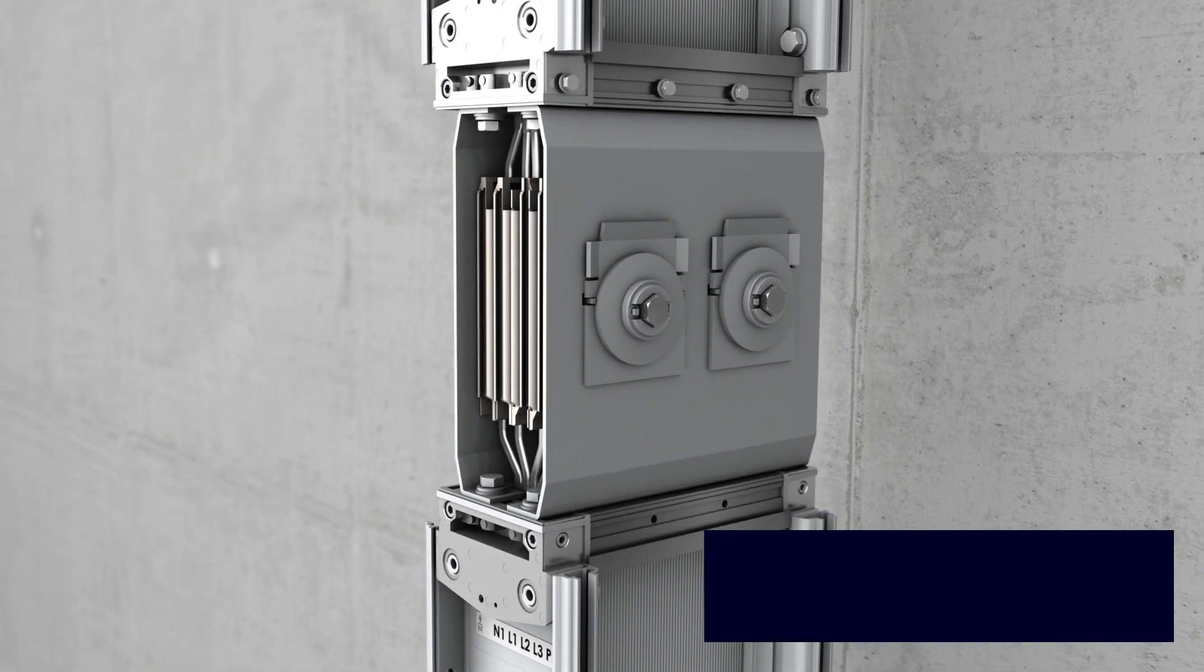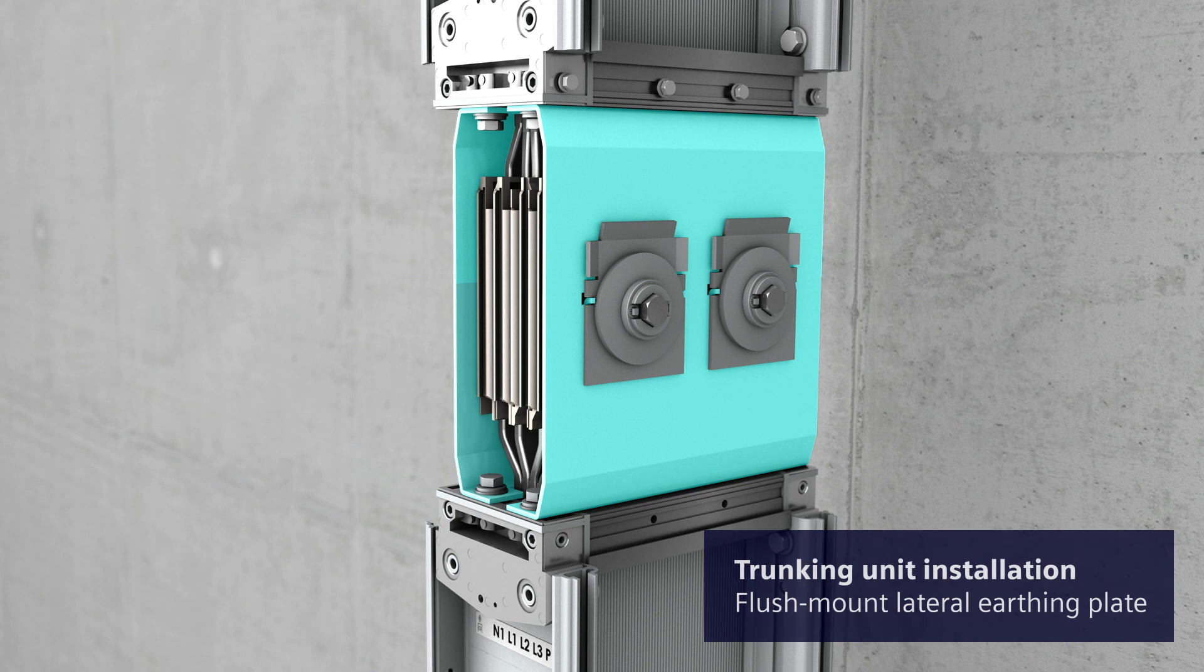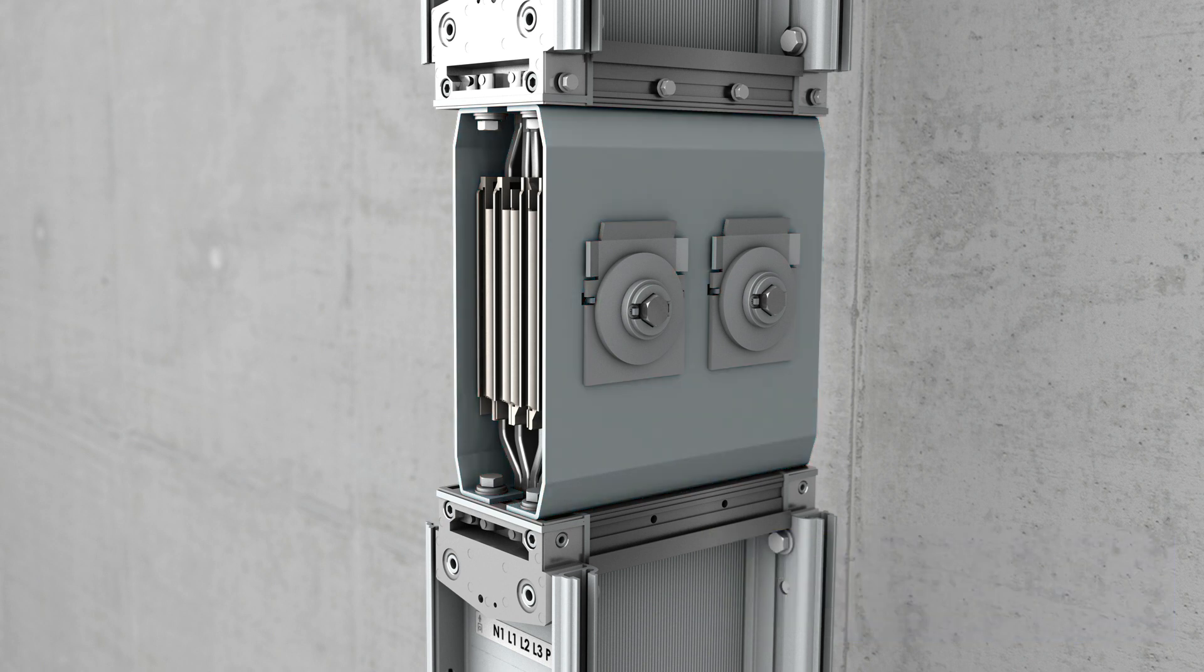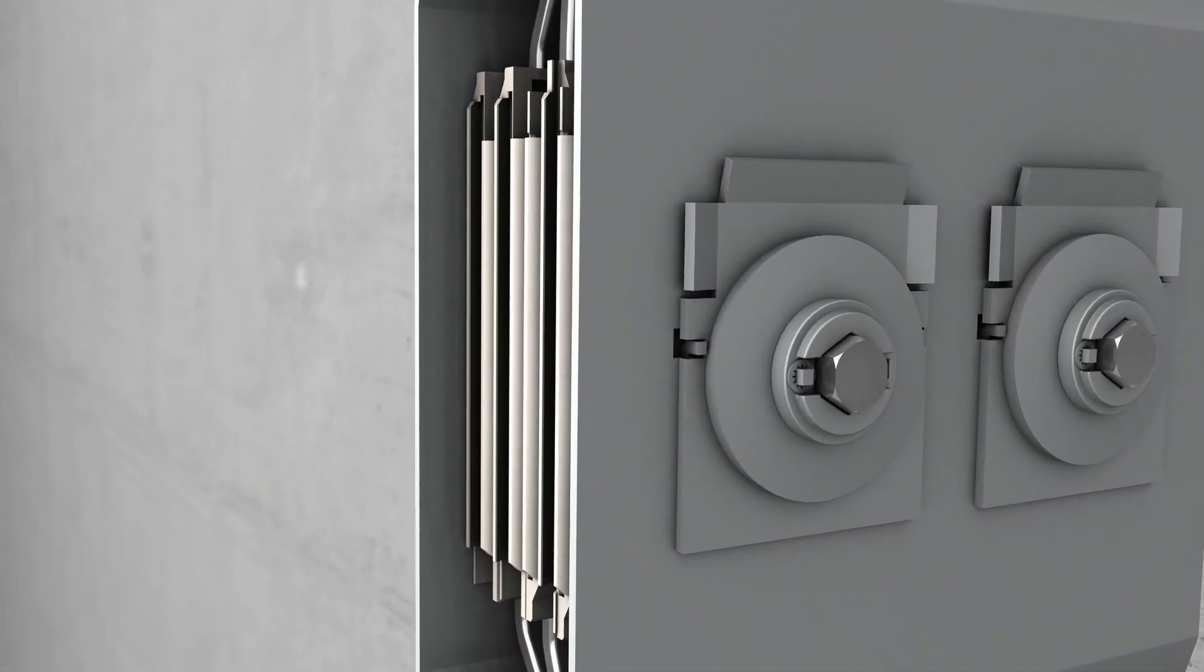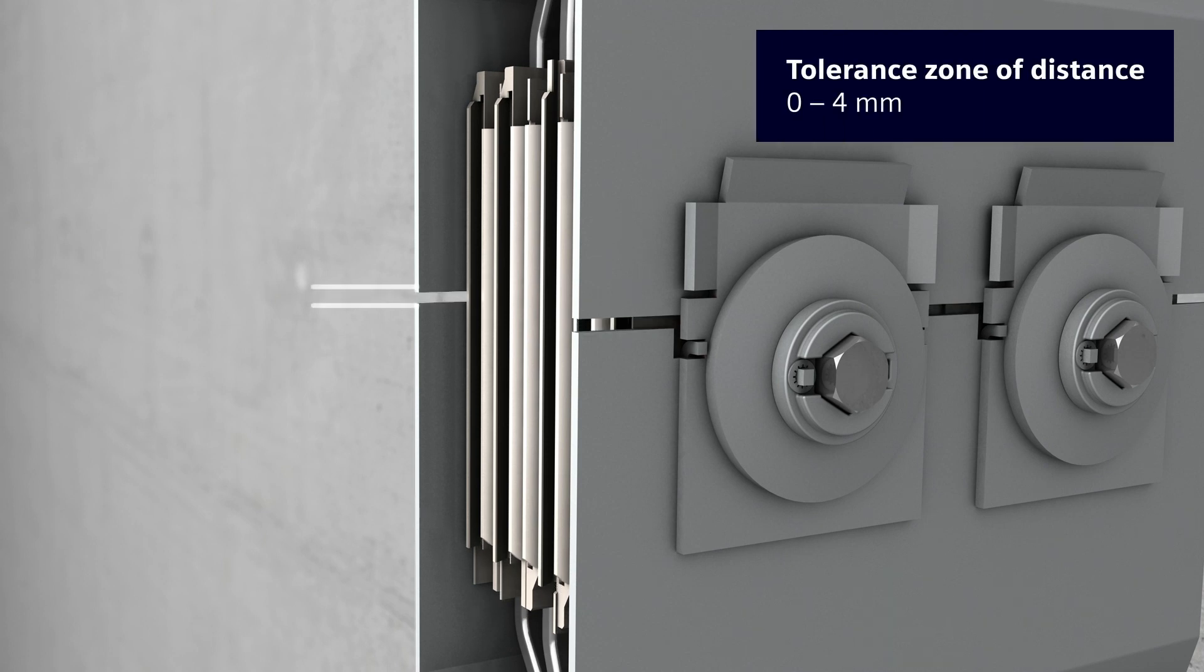Make sure to position the lateral earth side plates flush against the two trunking units. Check the distance between the two trunking units. The distance between the trunking units at the earth side guide plates must be within a tolerance of 0 to maximum 4 mm. The terminal block is then positioned correctly.